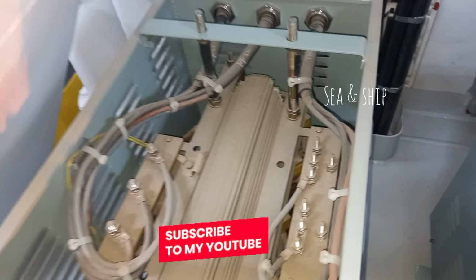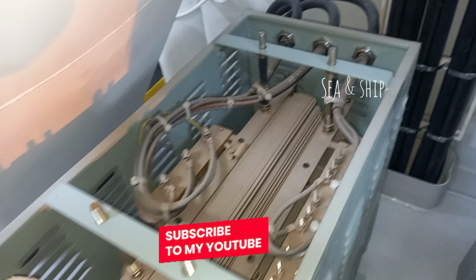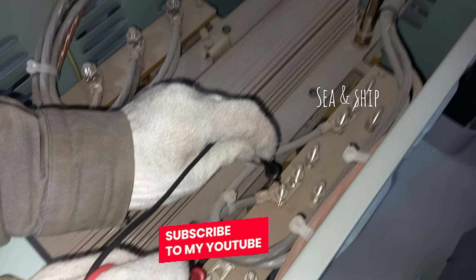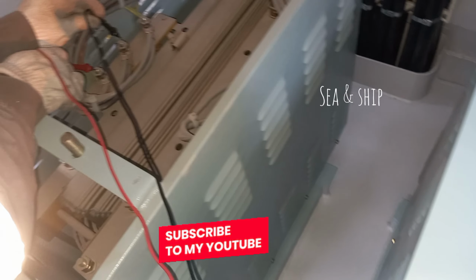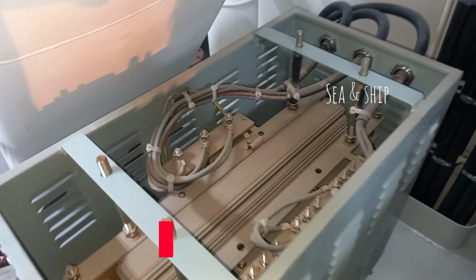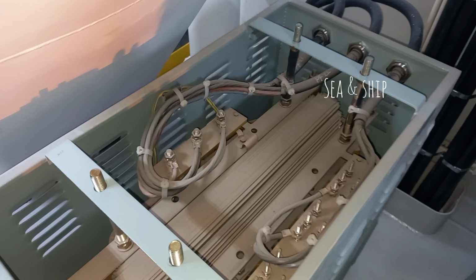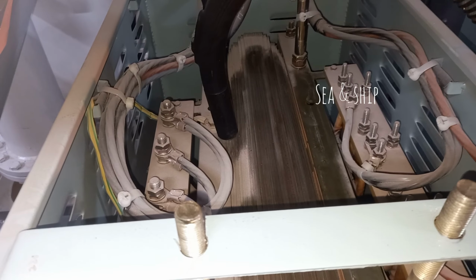After ensuring safety, carry out a visual inspection by checking for dust accumulation, loose connections, discoloration, burn marks, or any unusual smell. Then start cleaning using a vacuum cleaner to remove dust from windings and ventilation areas, and use a dry lint-free cloth or soft brush for tight spaces.